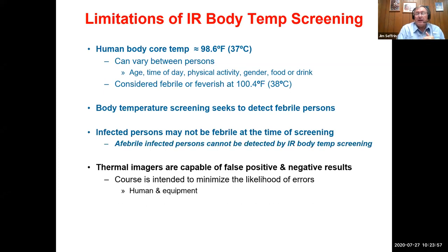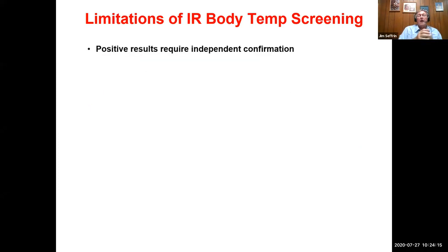One should also be aware that thermal imagers are capable of both false positives and false negatives. So this brief course today is intended to minimize the likelihood of errors associated with both human operators and the equipment that they utilize. When a person tests positive or sets off an alarm with our infrared body temperature screening imager, these positive persons testing positive require independent confirmation.